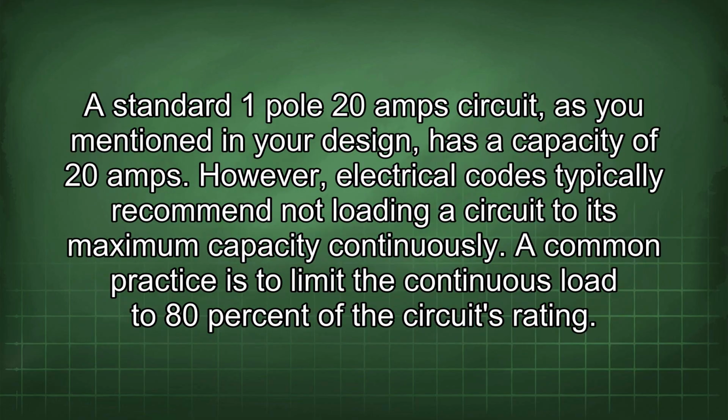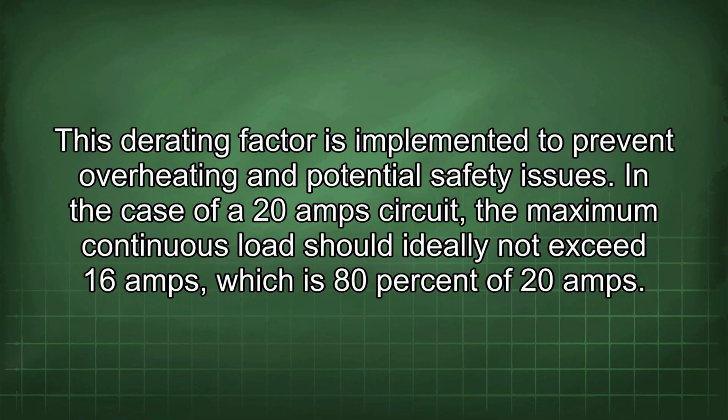A standard 1-pole 20 amp circuit, as you mentioned in your design, has a capacity of 20 amps. However, electrical codes typically recommend not loading a circuit to its maximum capacity continuously. A common practice is to limit the continuous load to 80% of the circuit's rating. This derating factor is implemented to prevent overheating and potential safety issues.